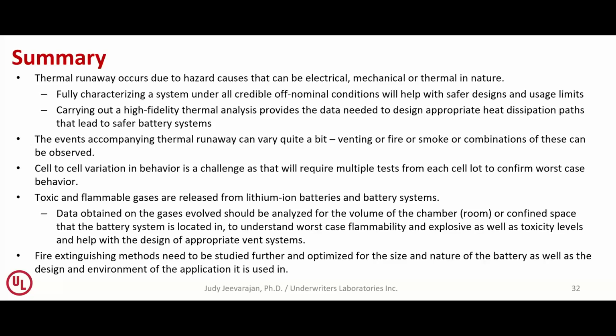Carrying out a high fidelity thermal analysis provides a lot of data. It helps you design appropriate heat dissipation paths, but it also tells you where to place thermocouples to capture worst-case temperatures in your battery pack, and what the thermal gradient is within the pack. If you see larger deviations or thermal gradients, you can look into designing it better or saving your battery.